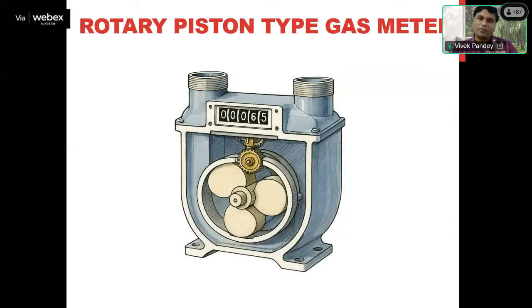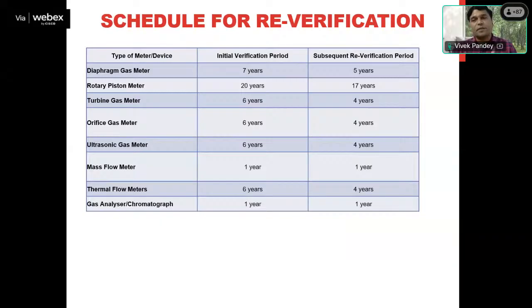Okay, so based upon the functioning of these gas meters as well as the technology used inside them, in our general rule the verification periods are defined. If you carefully observe this particular table, where I have not taken all of them but a few, you can see that the period of verification and re-verification is mentioned for these gas meters. That means after how much time the gas meter should be recalibrated and re-verified. You can see that in the rotary piston type meter technology, the initial verification period is 20 years and the subsequent verification period is 17 years. It is more than the other technologies used in gas meters.